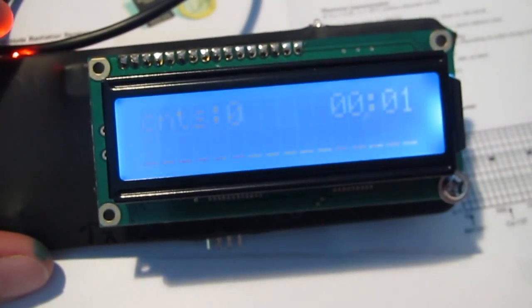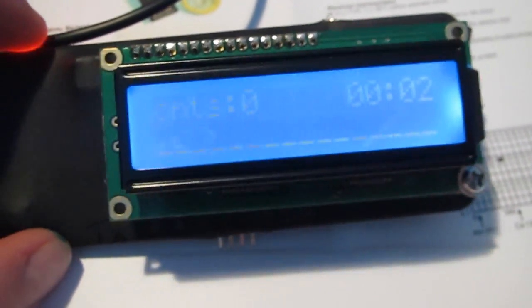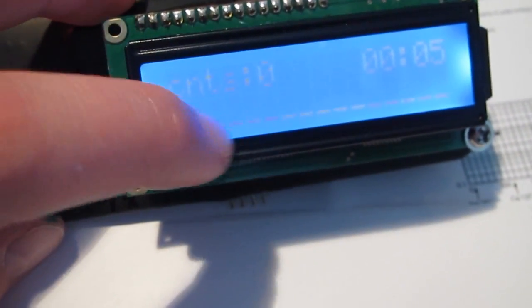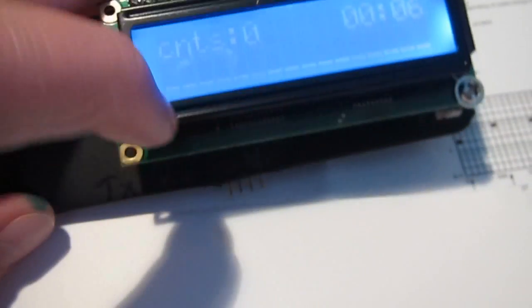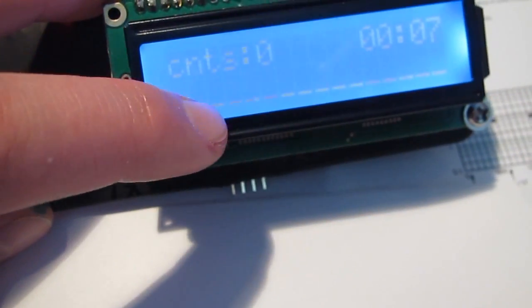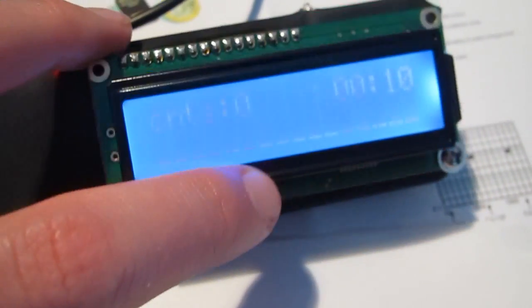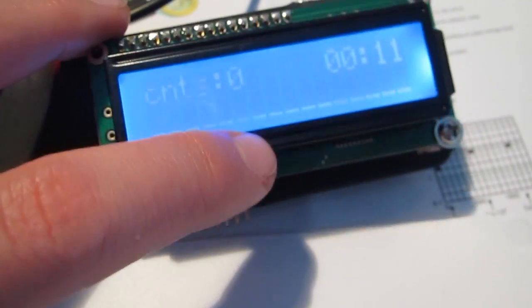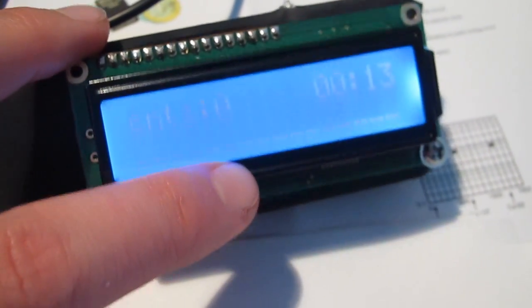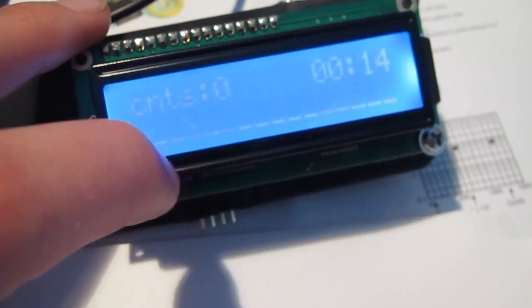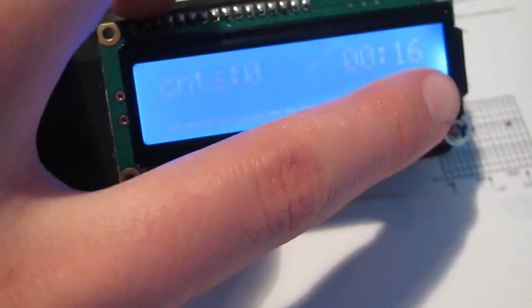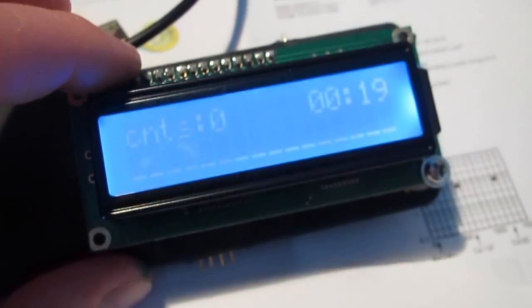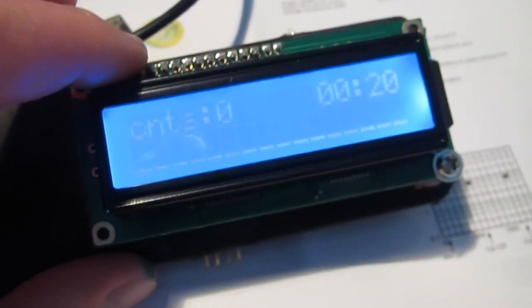So when checking x-rays with this device, we should have a broad range of energy pulses, even in the lower energy area here. Maybe not the first bins, but anything above that, because as I said the bins are not exactly assigned to a specific energy as of yet, but we should have a spectrum distributed over the entire area pretty much. So let's check that out.